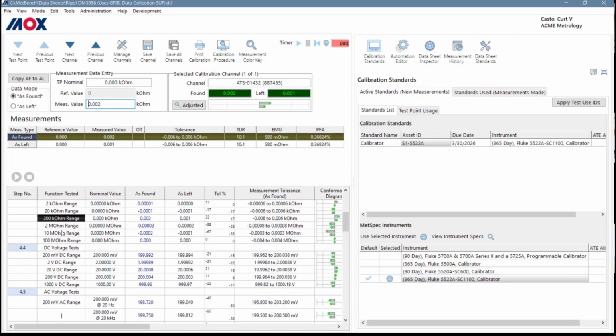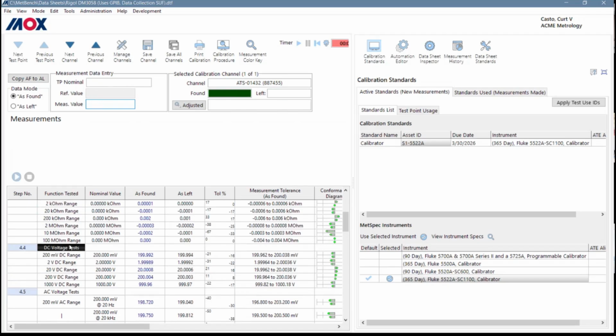All right, so what I'm going to do now is show you in a little bit more detail what I did, again in the order of time. I have this 5.5 digit data sheet, which is what's actually set up behind me over there on the 5522 calibrator. And on the top is that 5.5 digit DMM.